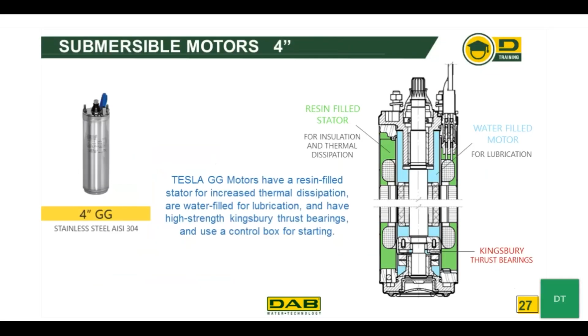The 4-inch GG Tesla motor has a resin-filled stator for increased thermal dissipation. It heats up less by using the resin-filled stator to dissipate heat out to the water that's moving past the motor more efficiently. They're water-filled for lubrication and have high-strength Kingsbury thrust bearings. They also use a control box for starting because these are 3-wire motors.